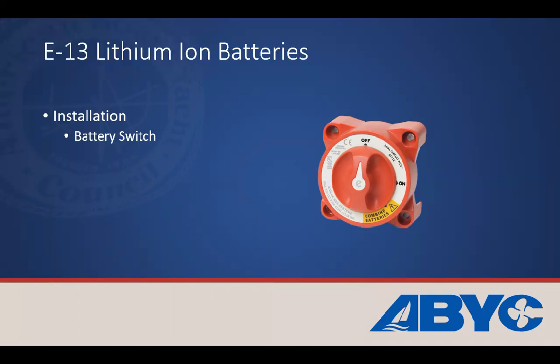Battery switch is another thing that I'm calling out. That's really an E11 thing. That's called out here as well. Again, because typically these are larger batteries, you're going to need a way to disconnect. Overcurrent protection, obviously, is called out by E11 in these systems, right? Overcurrent protection is to protect the conductor of the battery, and as I mentioned, secured properly.